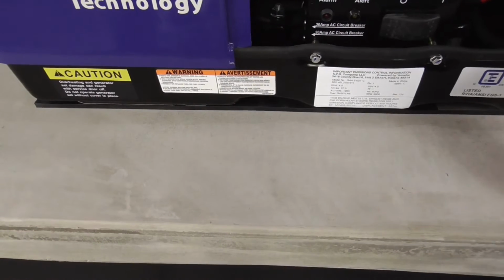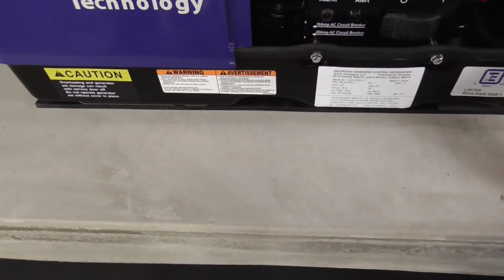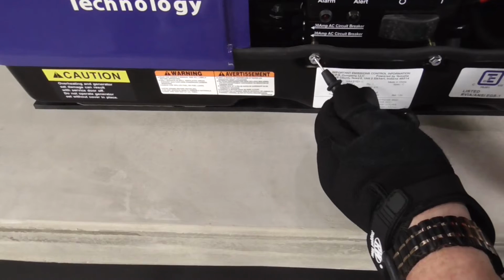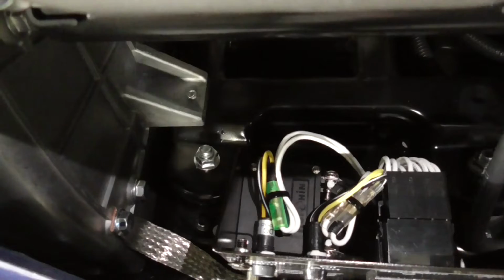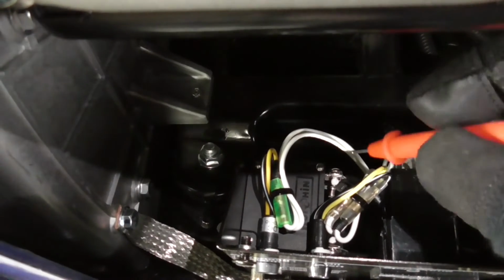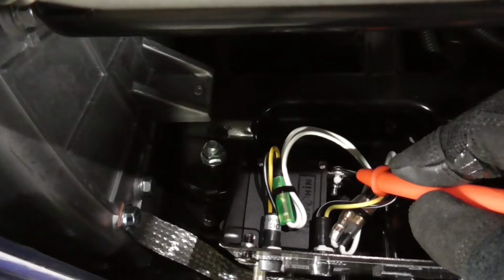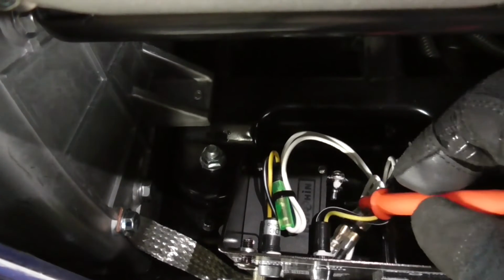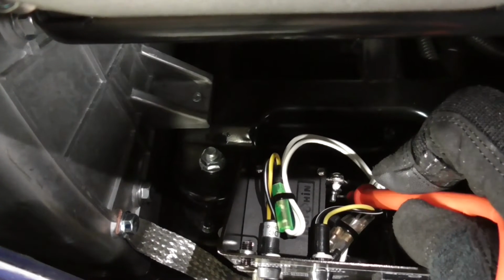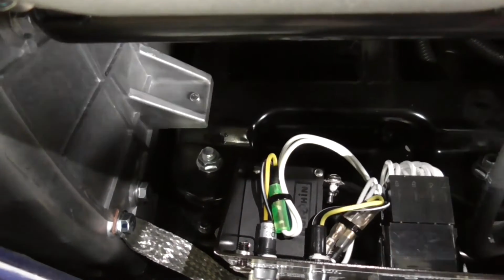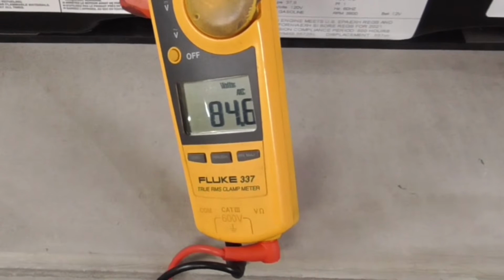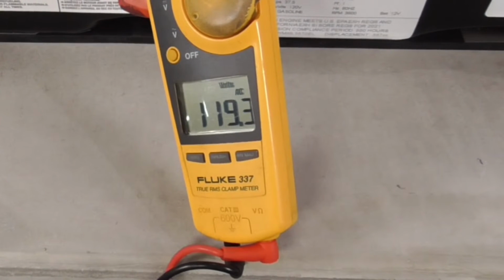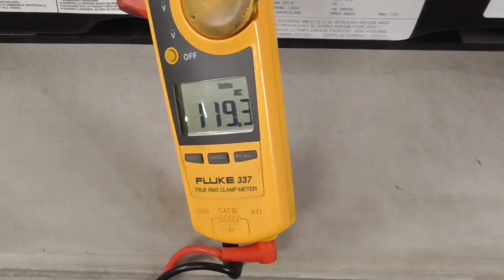Put one probe of your voltmeter on a good ground plane. A mounting bolt works well for this. Put your other probe on the output of the breaker. Each breaker should register approximately 120 volts on its output. If there's voltage here on the breakers, check your transfer switch.